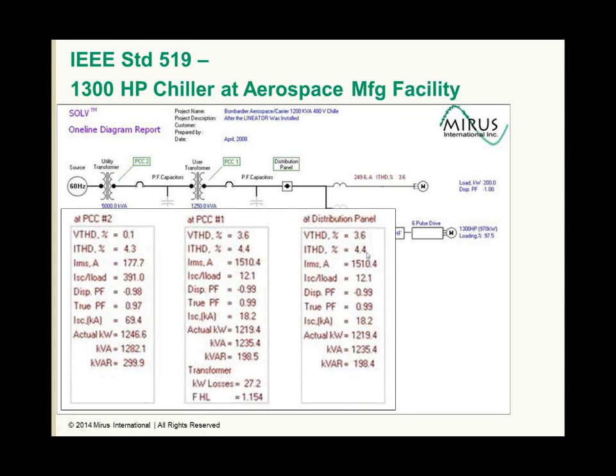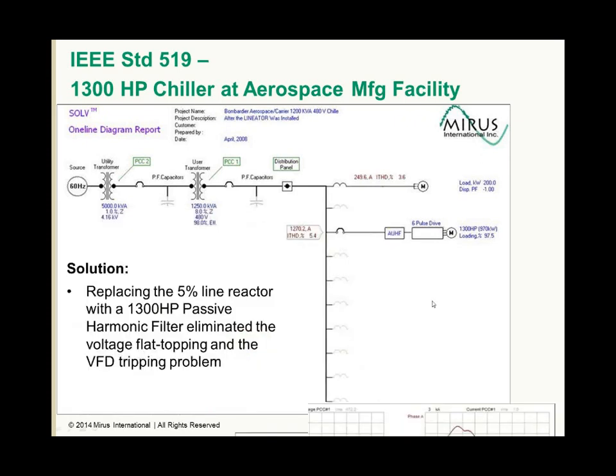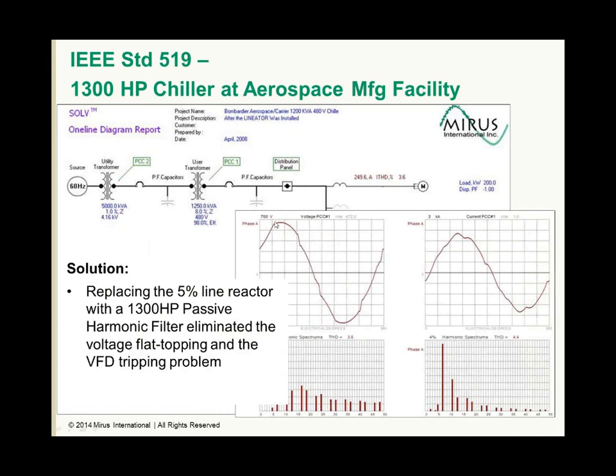So we see now the reduction in current distortion, dropping the voltage distortion. Our waveforms now, the voltage peak is restored, current is near sinusoidal. See the current spectrum here, the scale is only 4% maximum scale here, so you can see there's a little bit of 5th and 7th, 11th and residual harmonics, but it's substantially lower than it was before. And this allowed the chiller to operate without problems.